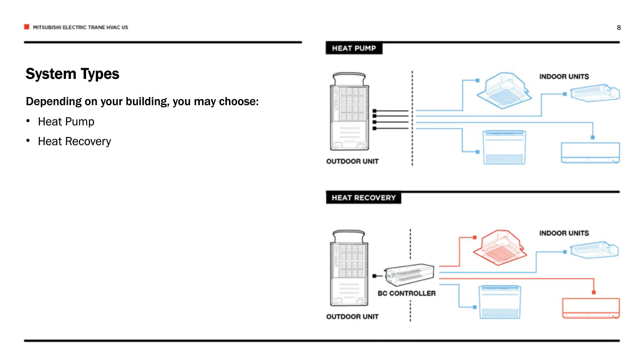Heat recovery systems provide simultaneous heating and cooling operation from the same system. These systems utilize a branch circuit controller, which acts as a means of transferring heated refrigerant from zones in cooling to those zones calling for heating and vice versa. Simply put, it can be seen as a traffic cop for that refrigerant.